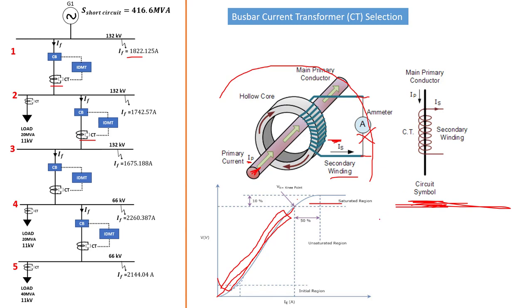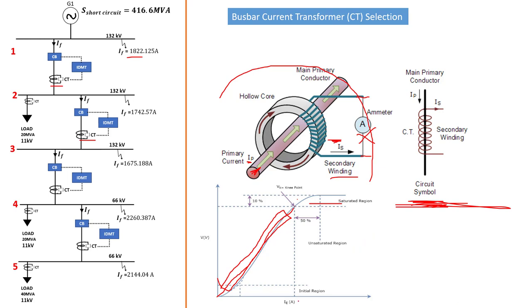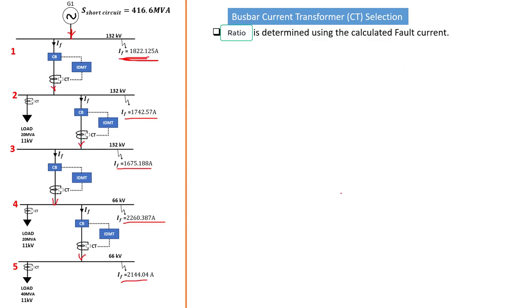That's what we call a saturation region — when the current transformer gets to that point, it becomes useless because it's not protecting anymore. So the purpose of protection is to ensure that as soon as we get out of the linear region and reach the knee-point voltage, your system must have already tripped to provide protection. We then move on to determine the turn ratio for our transformer, which must be according to the magnitude of the fault current on each of these bus bars. Our current transformer ratio must be determined using the calculated fault current on each bus bar.